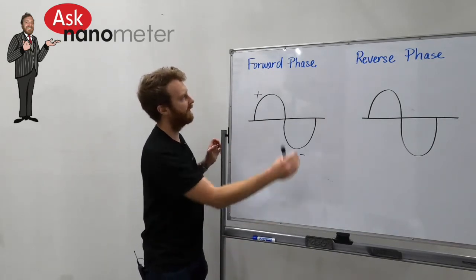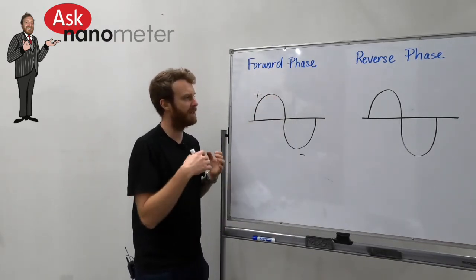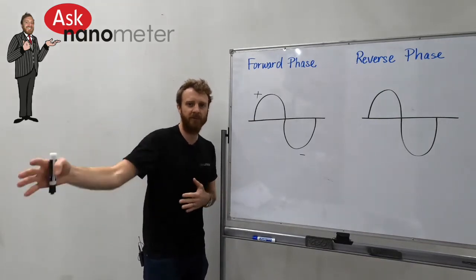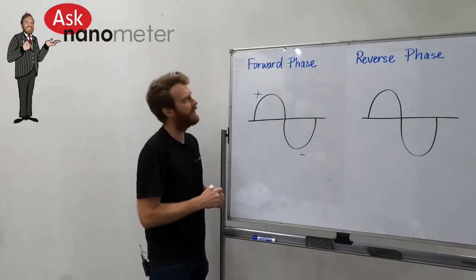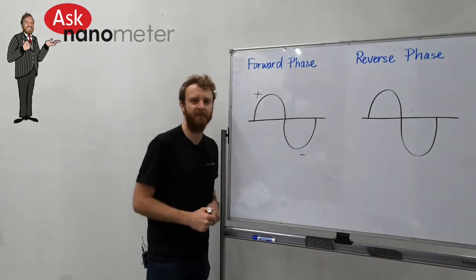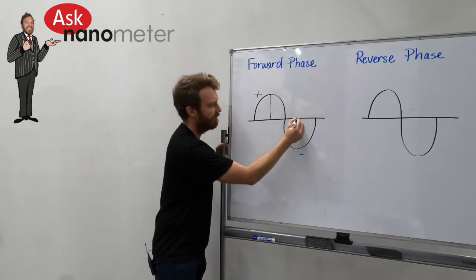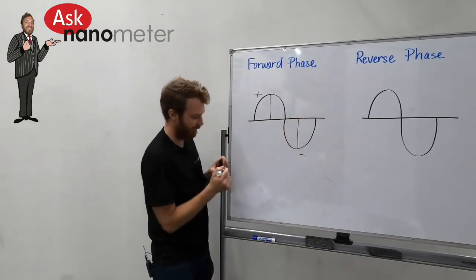When we attach a forward phase dimmer or a leading edge dimmer, what we're actually doing is manipulating that power in order to dim the driver that's attached to it. If we take the dimmer and set it to 50 percent, what it's effectively going to do is hack off the front side of the sine wave.